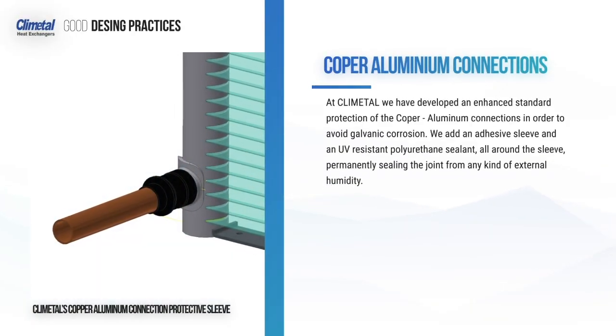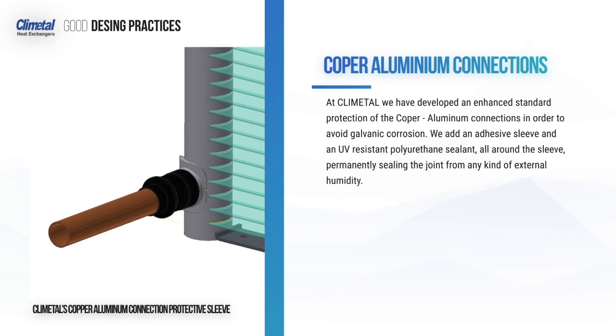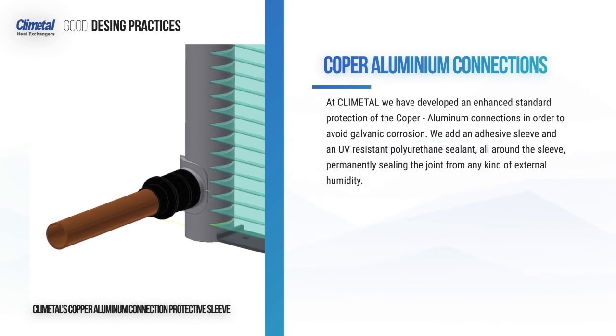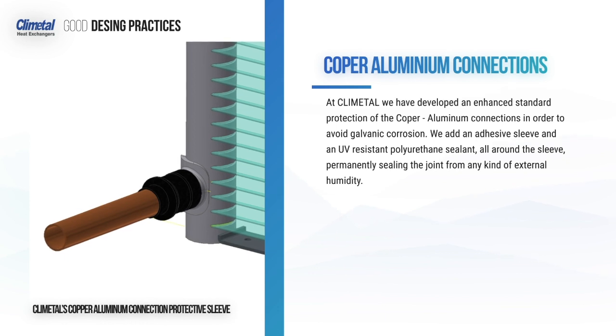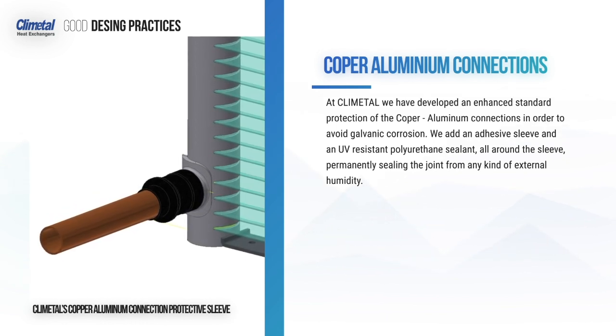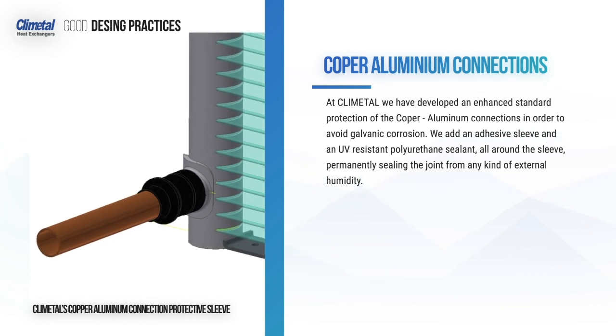At Climetal, we have developed an enhanced protection of the copper-aluminium connections in order to avoid galvanic corrosion. We add an adhesive sleeve and a UV-resistant polyurethane sealant all around the sleeve, permanently sealing the joint from any kind of external humidity.